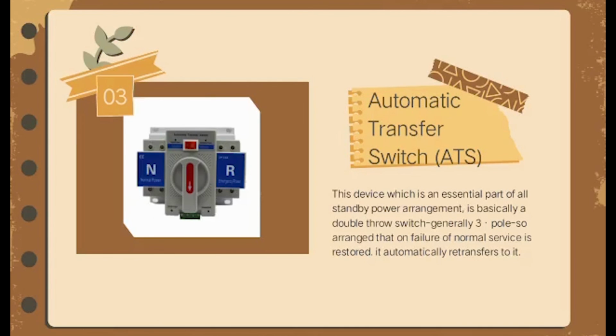And lastly, the automatic transfer switch. This device, which is an essential part of all standby power arrangements, is basically a double-throw switch, generally 3-pole, so arranged that on failure of normal service, when normal service is restored, it automatically transfers to it.